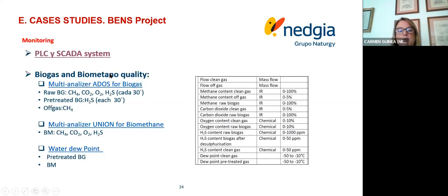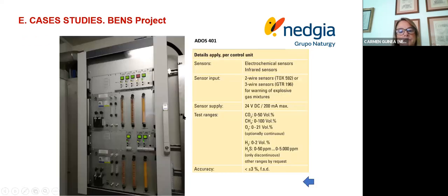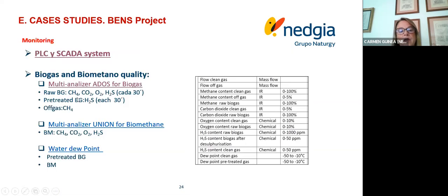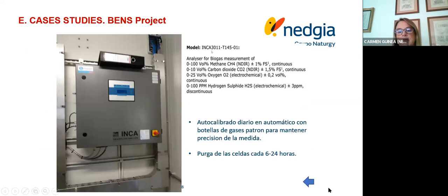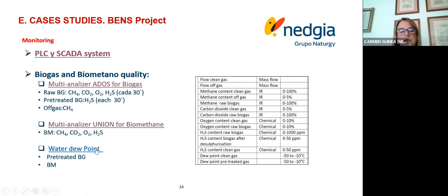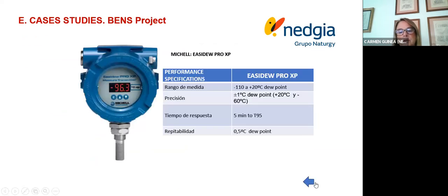The biogas and the biomethane quality is monitored by the following analyzers. This is the multi-analyzer for biogas that measures the methane, CO2, oxygen, and hydrogen sulfide every 30 minutes. And for the pretreated biogas, every 30 minutes it measures the hydrogen sulfide and the methane in the off-gas. The multi-analyzer for the biomethane measures methane, CO2, oxygen, and hydrogen sulfide. This is the analyzer. The water dew point, which is critical for the compressed biogas and for the membranes, is measured with this instrument.